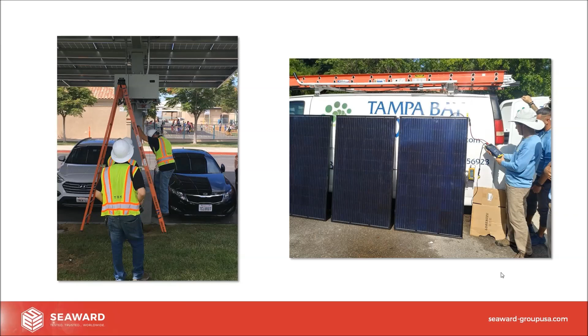So that's all well and good, it's going to improve the testing process. You don't have to use multiple tools, an insulation tester, a clamp-on. You're getting increased accuracy, you're able to calculate your expected values and compare them to your measured values with an educational approach. Then at the end of the day, we can come back into the office and use a tool such as SolarCert, which is going to generate a good string report for you. You'll be able to see performance ratios, fill factors, all the information you took on site. We can feed that into the software, tell it which panels and module we're going to be using, and it will give you a nice generation report.